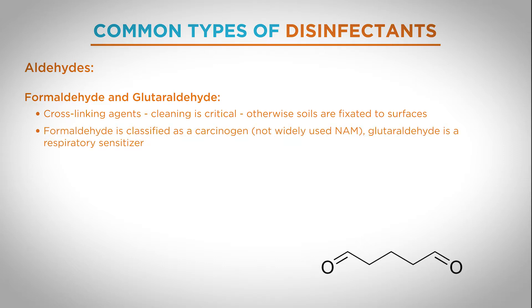Formaldehyde, although not used much in North America, is a carcinogen. Glutaraldehyde is formally recognized as a respiratory sensitizer, meaning continual exposure increases the chance of people developing asthma. This has been documented extensively in the literature, to the point where, in the human health field, the use of glutaraldehyde — which used to be the workhorse chemical for endoscope and instrument disinfection — has dropped dramatically. In fact, some countries, like the UK, have banned it for that use.